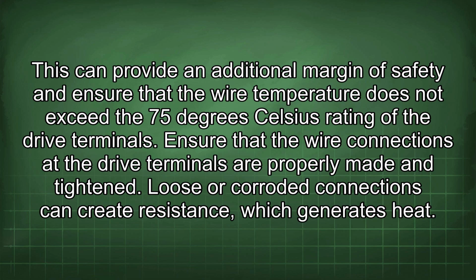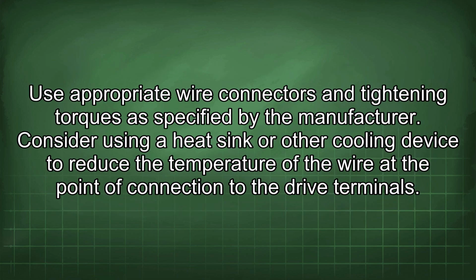This can provide an additional margin of safety and ensure that the wire temperature does not exceed the 75 degrees Celsius rating of the drive terminals. Ensure that the wire connections at the drive terminals are properly made and tightened. Loose or corroded connections can create resistance, which generates heat. Use appropriate wire connectors and tightening torques as specified by the manufacturer.